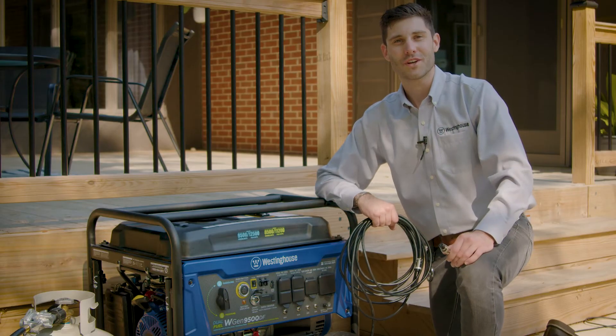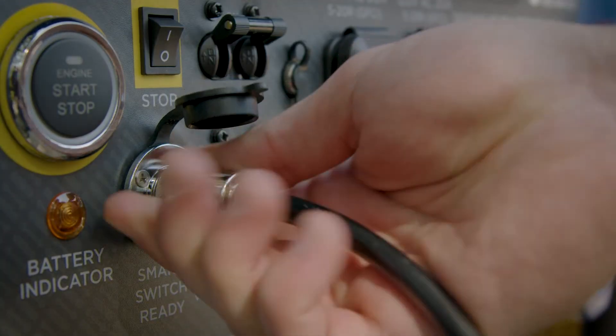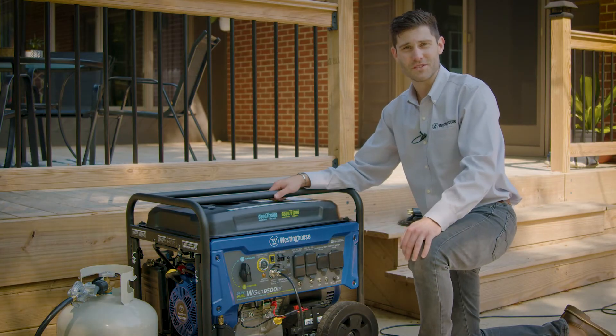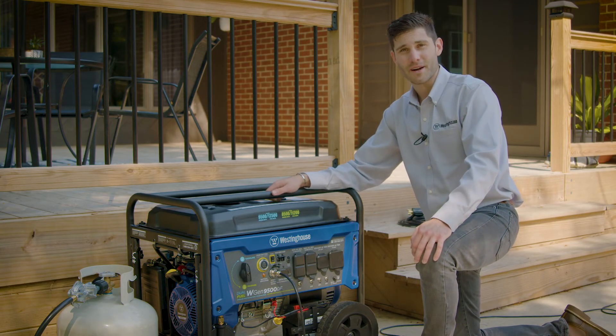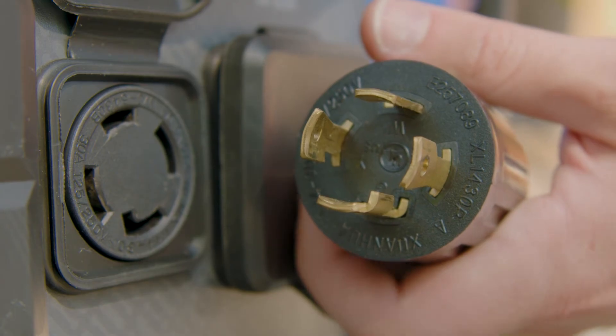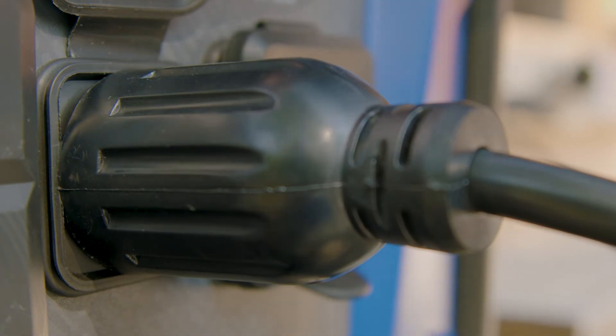Now we're going to hook up your cables. Find your generator control cable and hook it up to the Smart Switch outlet on the generator. As long as the Smart Switch is plugged into home power, the control cable will ensure that your battery stays charged while your generator is standing by. Now hook up the four prong power cable from the Smart Switch to the generator. Make sure you line up the extra tab on the plug to the tab on the generator and twist the plug for a secure connection.